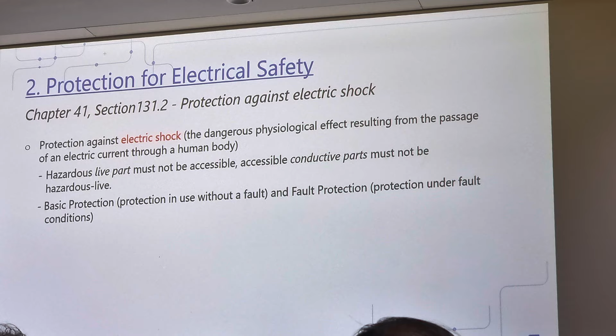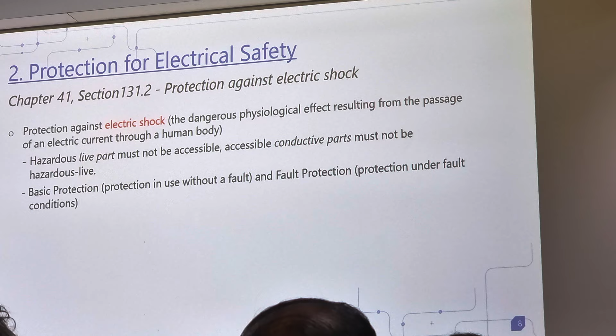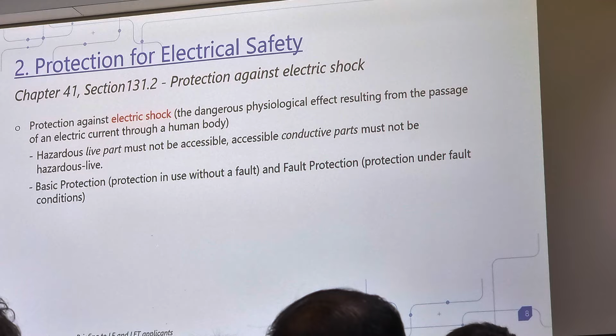This is direct electric shock protection. Now the second part is that accessible conductive parts must not become hazardous live. Now what is a conductive part? If you read SS638, they talk about exposed conductive parts and extraneous conductive parts, which may include trunking, cable tray, water pipe - because all these are conductive parts.